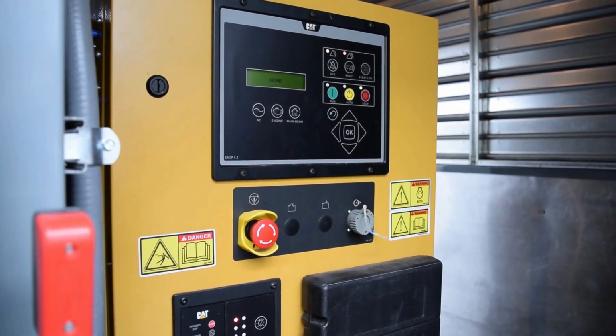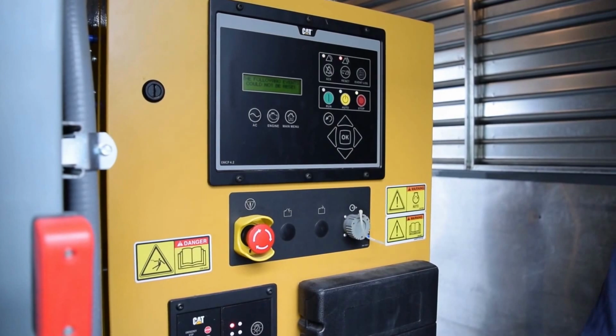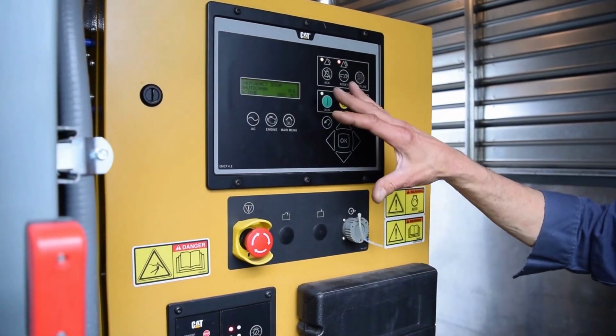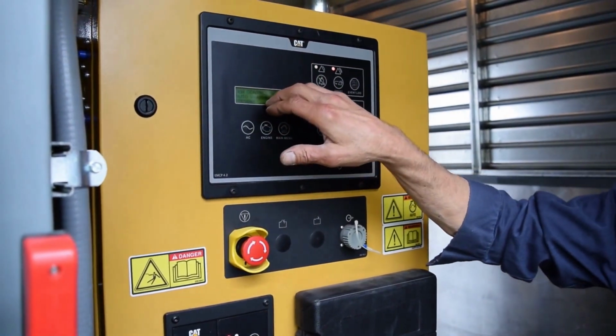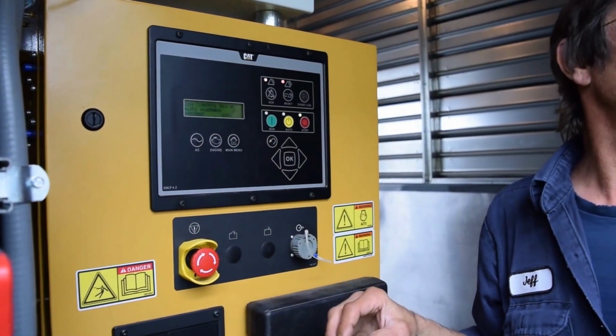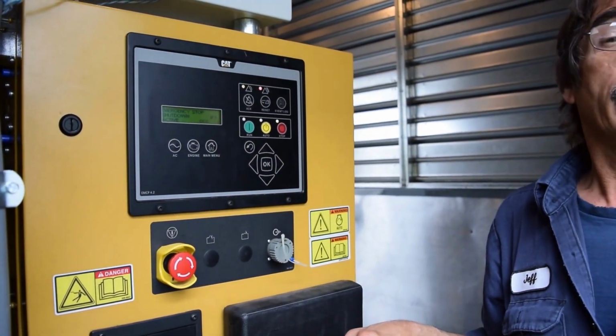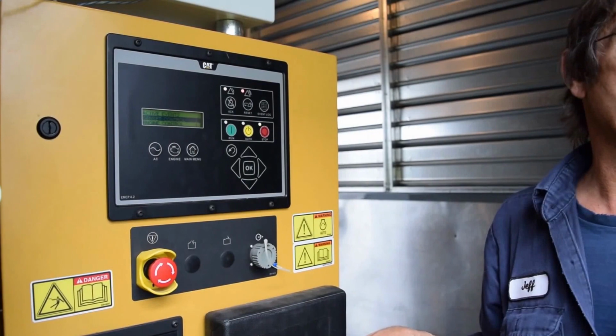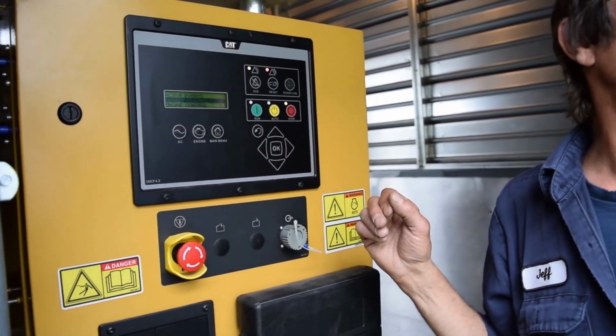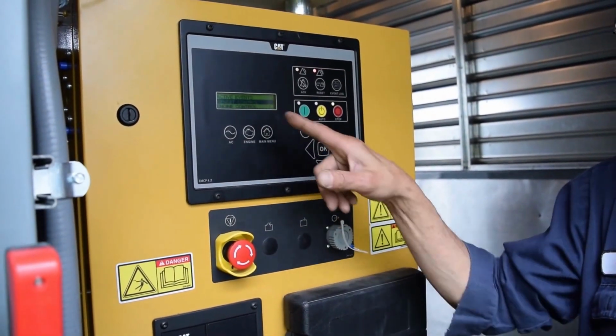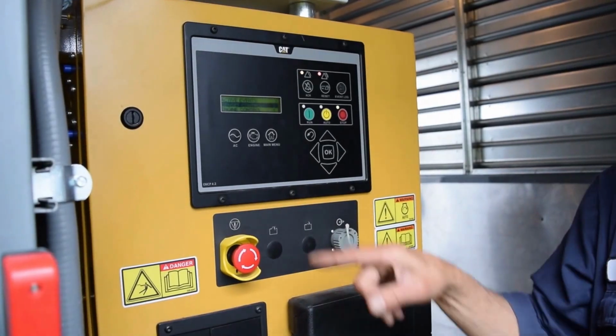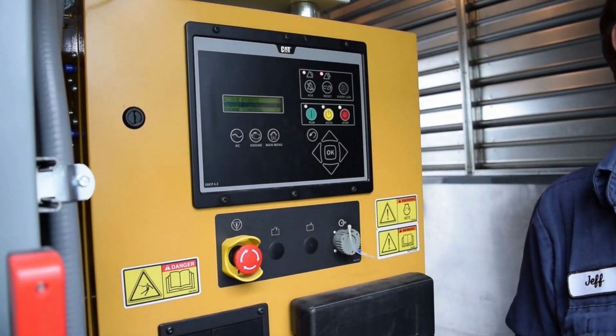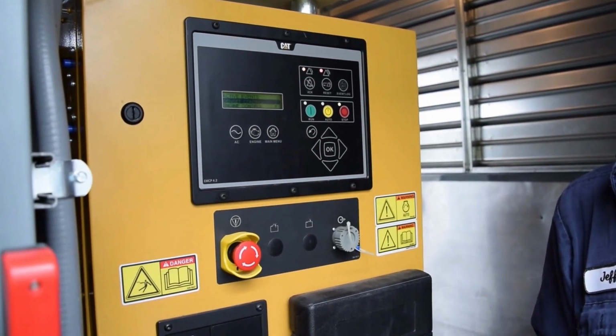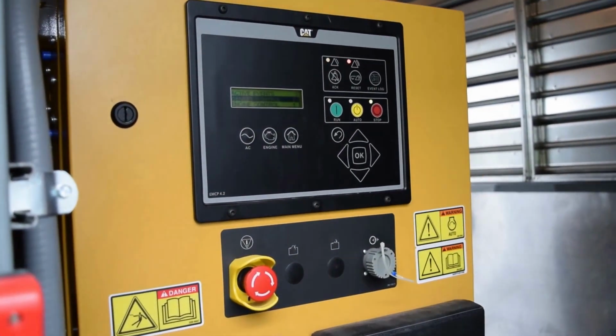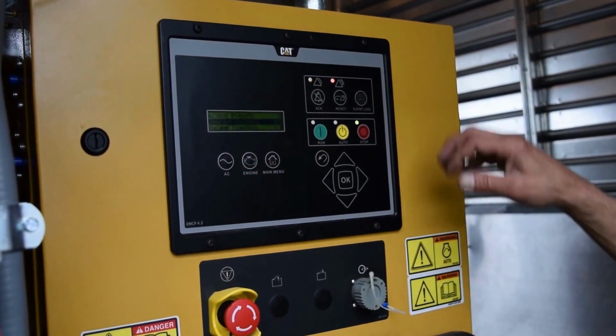And that is what happens with the remote e-stops outside. And that's why you'll see on this, you'll see emergency stop shutdown active. You will see remote emergency shutdown active. There is also one, and that one says on the container, and there is a third one that's down in the Fire Command Center. So on your panel, if that one is depressed, the writing will come up, emergency e-stop, Fire Control Center. So you know which one had an issue.